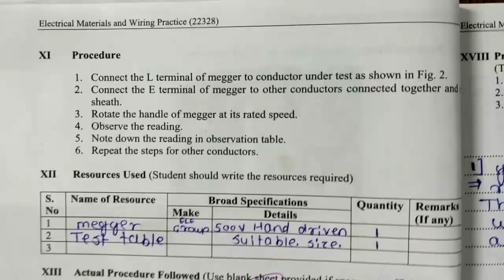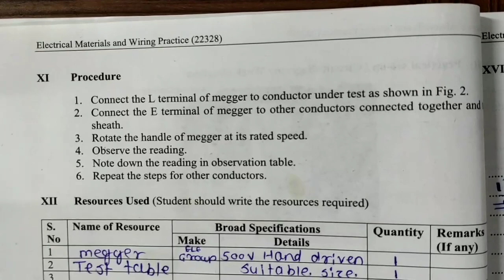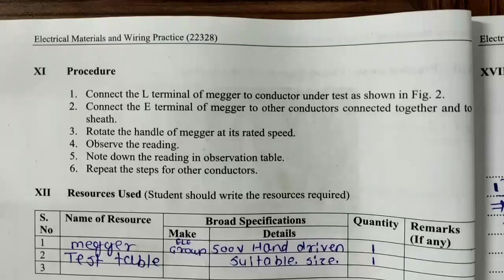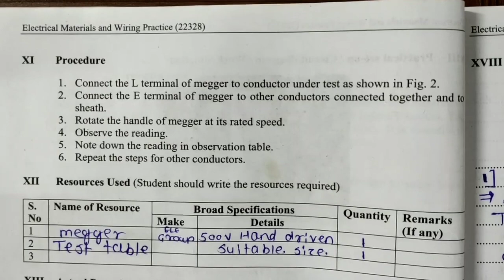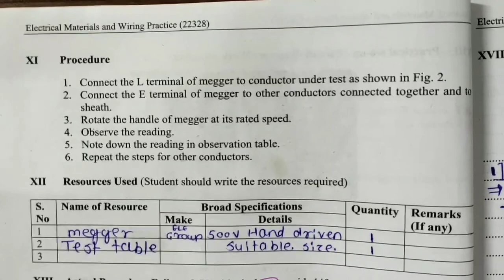In order to perform this practical, the following procedure is followed. So the procedure: connect the L terminal of the Megger to the conductor under test as shown in figure 2. Connect the E terminal of the Megger to the conductors connected together and to the sheath. Rotate the handle of the Megger at its rated speed. Observe the reading. Note down the reading in the observation table. Repeat the step for the other conductors.